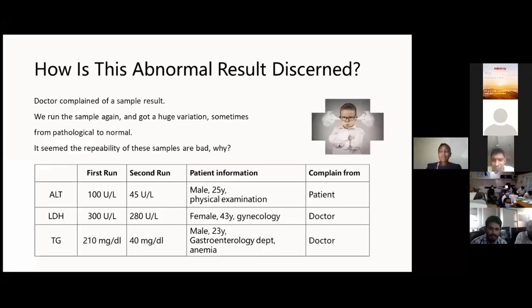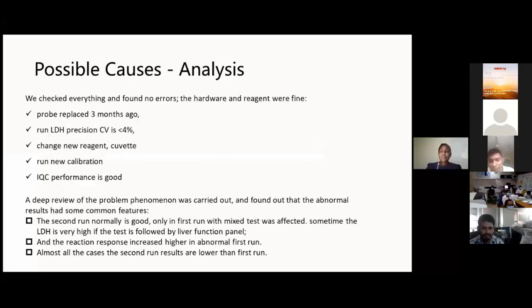Then with triglycerides, one sample would read 210, and on the second run the same sample would give a result of 40 mg per dl. We didn't want to continue like this. We needed to get the root cause, troubleshoot, do the corrective action, and also put a preventive action in place so that in the near future we don't face such concerns, which were legitimate concerns anyway.